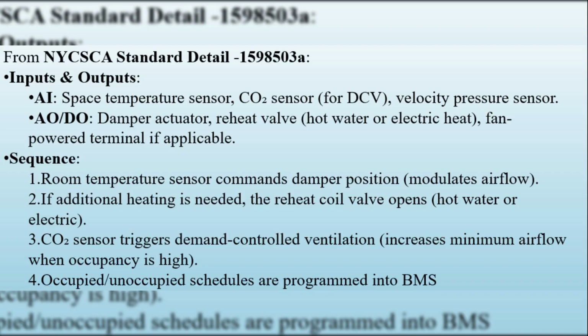Control strategy. Here's how the control sequence plays out. The VAV box reads signals from a room temperature sensor, a carbon dioxide sensor, and its own airflow sensor. Based on that input, the controller moves the damper to modulate airflow. If the room needs heating, the hot water or electric reheat coil opens up to warm the supply air. If carbon dioxide levels rise, meaning more students are in the room, the box increases the minimum airflow to bring in more fresh air. And the whole system runs on a schedule, switching between occupied and unoccupied modes automatically.